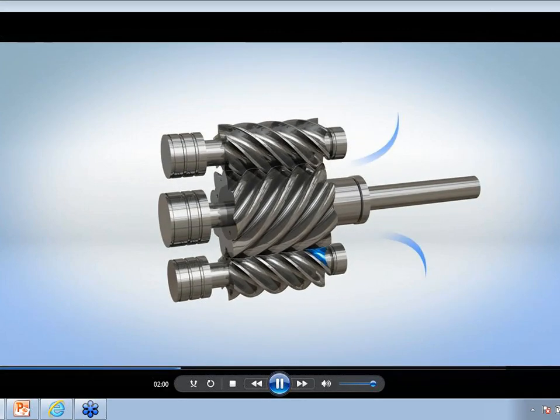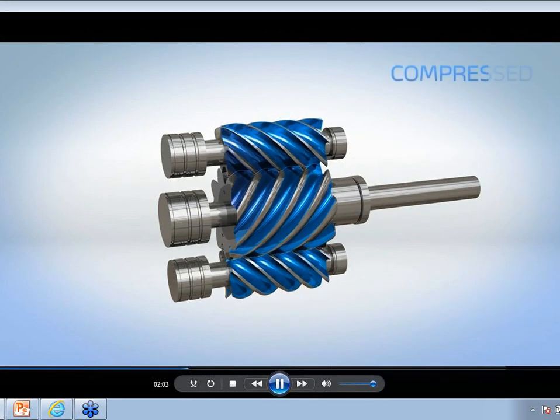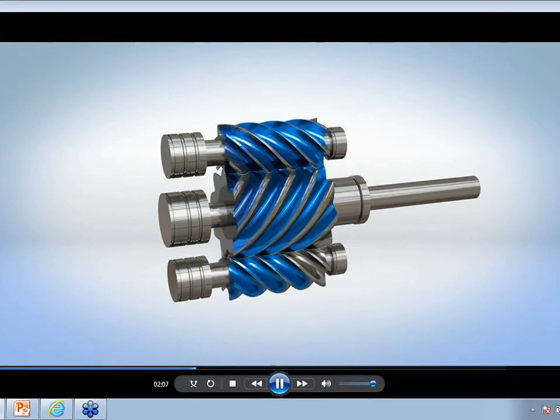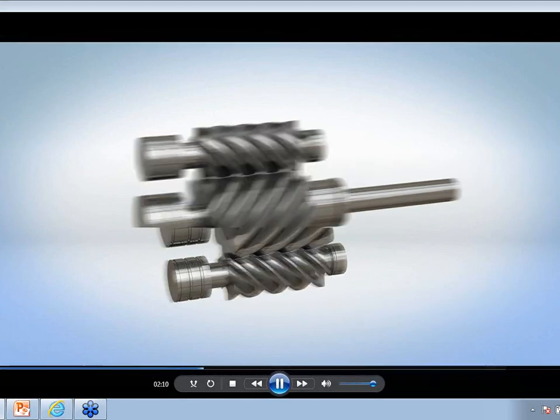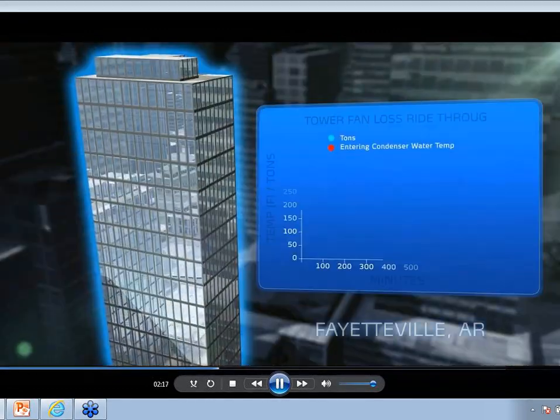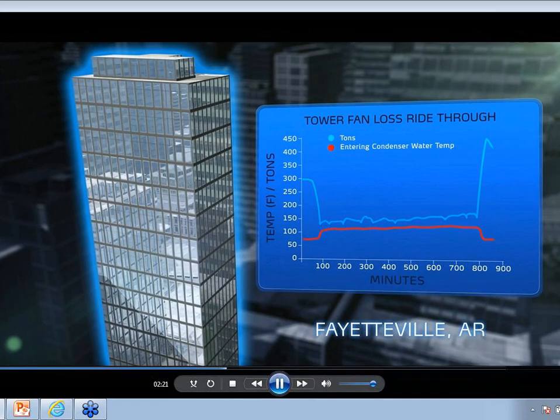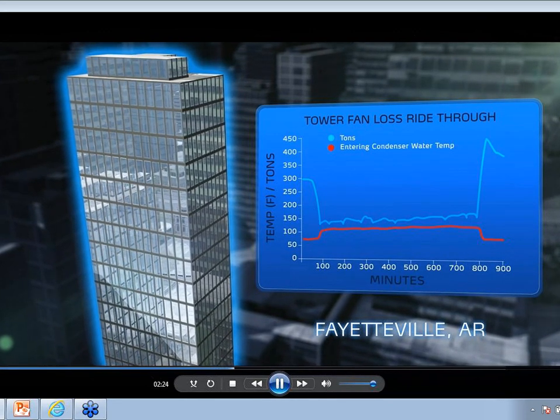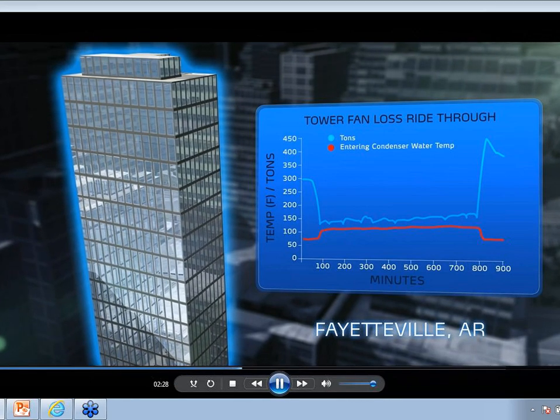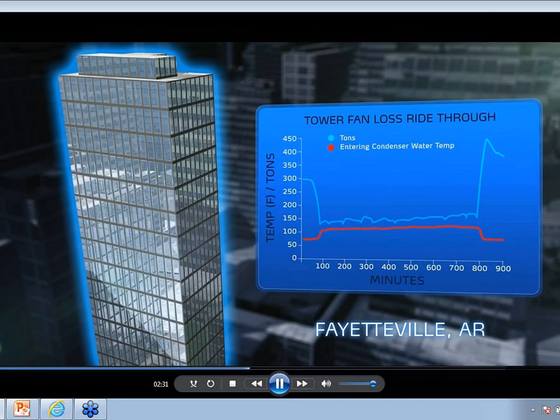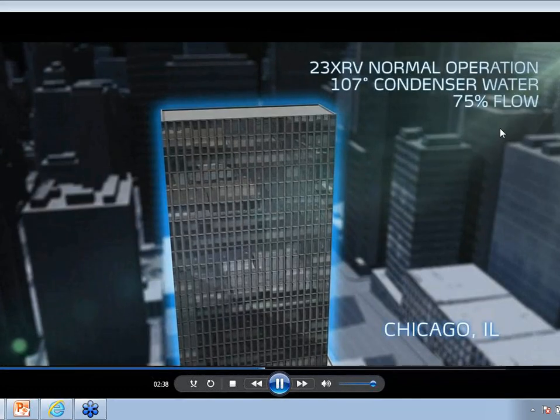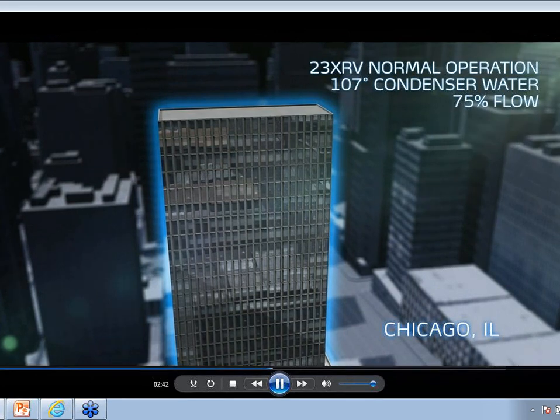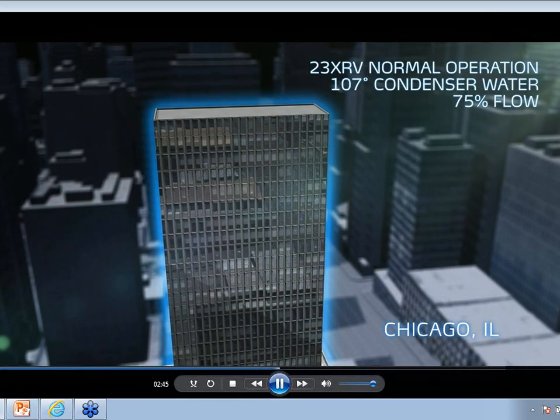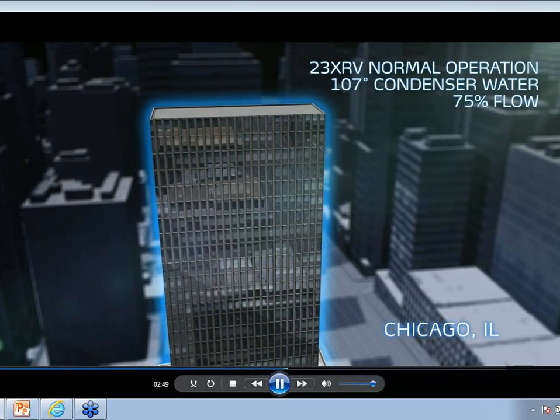As the rotors spin, refrigerant gas is drawn into a confined volume, compressed, and then discharged. This positive displacement compression process provides more robust and flexible operation. In 2005, field data recorders in Arkansas documented 23XRV operation without any operable cooling tower fans. The chiller endured entering condenser water temperatures of over 105 degrees during the 12 hours it took to repair the tower fan. The 23XRV chiller operates through conditions where other chillers would simply shut down. The machine is running without issue. It has 107 degree entering condenser water temperature to the chiller itself. Basically what they find out is that it's running about 75% flow, and there's also some other issues with the tower itself.